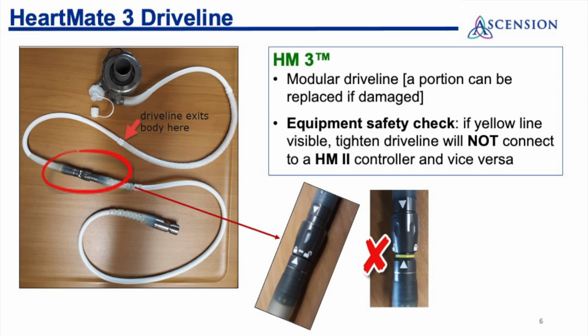HeartMate 3 has an updated driveline design with a section that can be replaced if damaged to avoid surgery and pump replacement. You'll need to check that this connection is locked and that the yellow line is not visible. If it is, lock it. When prepping a patient for transport, make sure the driveline is secured to prevent pulling or tugging.